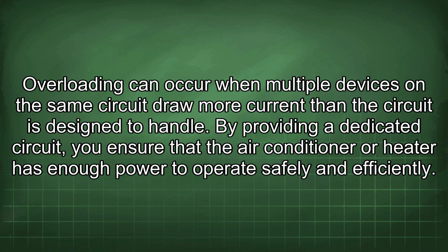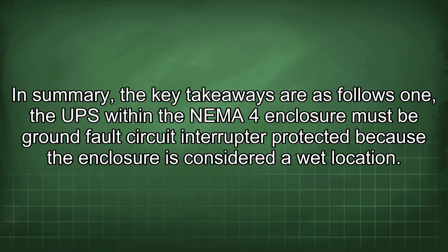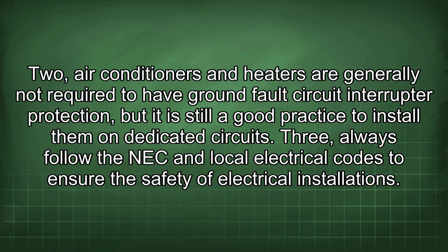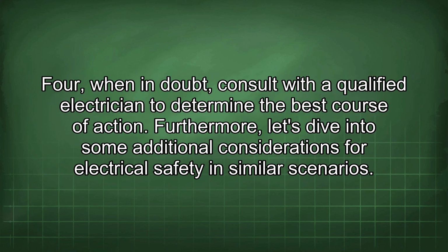In summary, the key takeaways are as follows. 1. The UPS within the NEMA 4 enclosure must be ground fault circuit interrupter protected because the enclosure is considered a wet location. 2. Air conditioners and heaters are generally not required to have ground fault circuit interrupter protection, but it is still a good practice to install them on dedicated circuits. 3. Always follow the NEC and local electrical codes to ensure the safety of electrical installations. 4. When in doubt, consult with a qualified electrician to determine the best course of action.